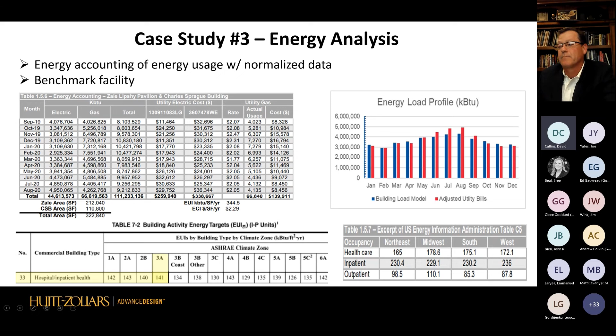We can start comparing our building load, what we came up with, to the utility bills. They're pretty close. The main thing is we're looking at the performance of the building, and that's this EUI, Energy Utilization Index, and the cost index. 344,000 is a lot. That's 344,000 BTUs per square foot per year. And then you say, okay, what should it be? If it's actually down in Texas, it should be like 140, and the DOE says, okay, if it's over here, we had half inpatient, half outpatient. So I'm thinking, yeah, it should be about 150 or so. So they're much higher than they should be. And so now we're able to go to the manufacturer. Now this is not in our model.